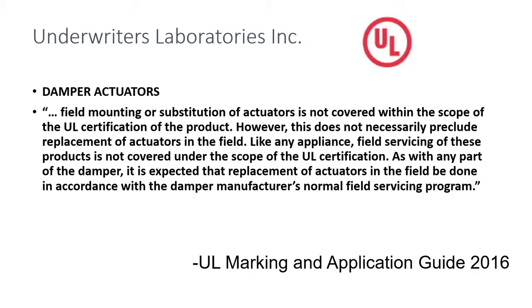Yeah, the head of the California State Fire Marshal's office, when I was talking to him about this, said, use common sense, fix it. I haven't run into a single fire marshal or city inspector that has said anything different. It's usually been a contractor who brings that up, and most of the time that's been a mechanical sheet metal contractor. Yeah, well, they're being careful and they don't know the laws, and people are afraid. I want to write an article called Fear of Fixing, because I get a lot of people afraid to repair their fire smoke dampers. They should be afraid not to repair them. We've got a few things backwards. Next.